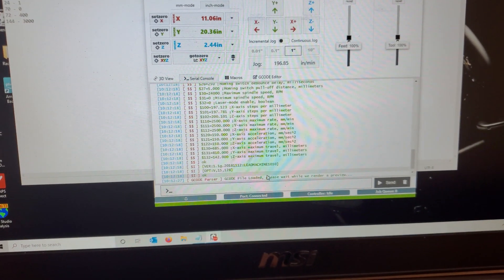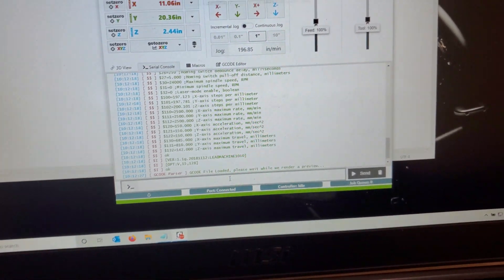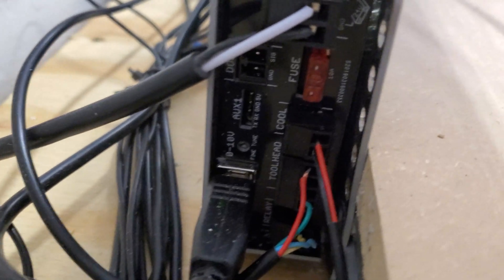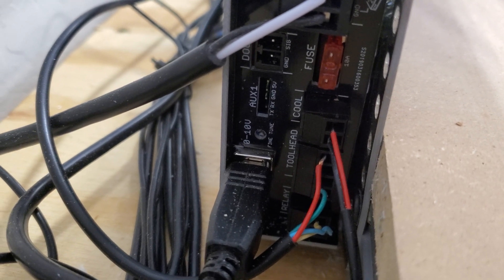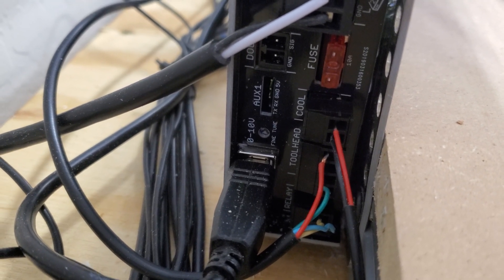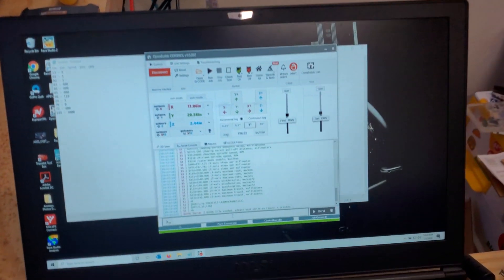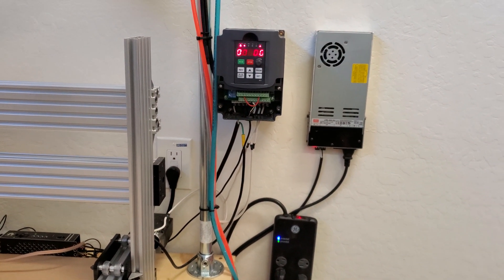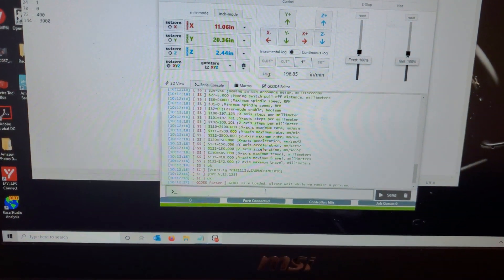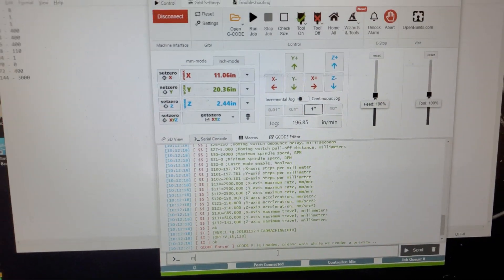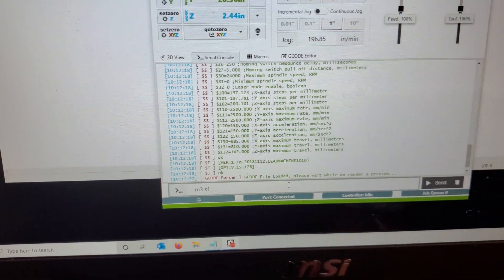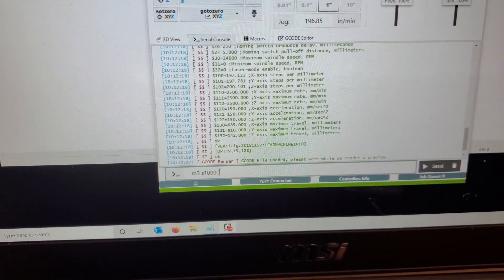The 0 to 10 volt line will need some fine tuning as well. On the back of your controller, right above the, kind of hard to see here, but see that 0 to 10 V? There's a little pot switch right above the USB connection. That controls how much voltage is coming out. So what I found the easiest way to do it, rather than hitting the ground and a 0 to 10 volt line with a multimeter, is just come into here. Once you get everything set up, you can go M3S, we'll go 10,000, hit enter.